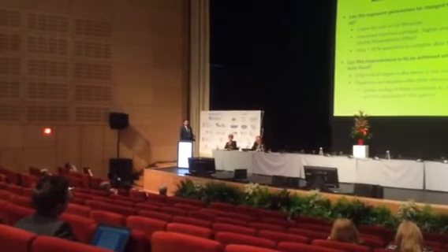The next question I had to answer was whether or not this improvement in image quality could be achieved whilst keeping the patient dose fixed. And the only critical organ in a paediatric extremity is a very small fraction of the red bone marrow, and they offer very little attenuation. So these lower energy X-rays that would normally be absorbed in the superficial tissue are actually contributing positively to the image.